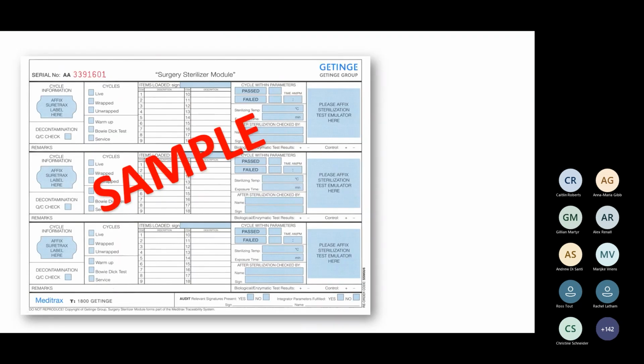So now when we're filling out the book, we're looking at the right-hand side. So we're saying whether the cycle passed, what the sterilizing temperature was, so what the highest temperature was during the sterilization cycle, the time it held for, which was 4 minutes for that particular printout that we looked at before, the name of the person who checked the load. So you write your name, you sign, and then if you affix an indicator, a class 6 indicator, or whatever, if you've used it there, you can put your tracking labels in there as well. Or you can attach your printout, whatever you want to do. If you don't have a printer, that's fine too. Most modern sterilizers have USBs now that record all the cycle information. So long as you're keeping that cycle information, you're seeing on the machine that it's coming up confirmed that it's passed the cycle, you can go back and check the cycle information via the cycles recorded on the USB stick.